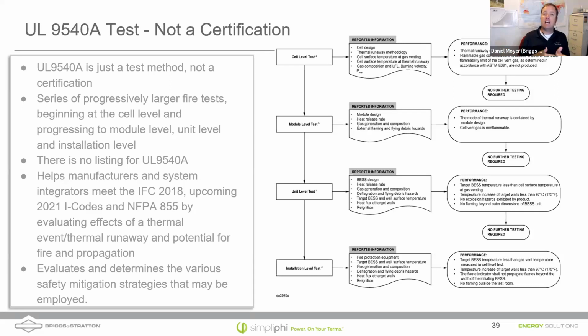They replicate those tests at a module level, a unit level, and if needed, a system level that integrates fire mitigation strategies like sprinklers or built-in fire extinguishers, or deflagration radiuses, which are explosion radiuses. What happens in this test informs the UL 9540 certification and what our separation distances may need to be. How well we do at UL 9540A may allow us to circumvent NFPA 855 requirements, which state you can only have a certain amount of kilowatt hours in one location. We've proven that we can have more than that without causing an unmitigated fire potential.